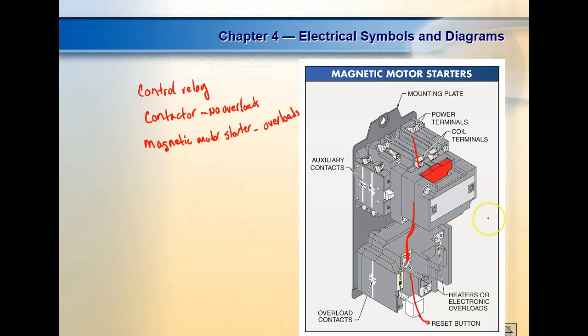So all the current goes through the overloads, and it senses that current, but it doesn't sense it like a breaker does. A breaker, if it's rated at 15 amps, then by George, if it sees anything over 15 amps, it's going to do what? It's going to pop. If you've got a fuse rated at 15 amps, as soon as it sees it, especially fast blow fuses. We do have some slow blow fuses, by the way. If you work with power supplies or anything like that, you should use a slow blow, because it's got all these big capacitors on there, and they have to charge up when you first turn them on. If you put a fast blow fuse in them, odds are the first time you turn it on, it'll blow the fuse.